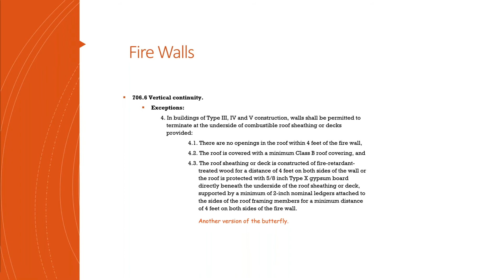The roof is covered with a minimum Class B roof covering, and the roof sheeting or deck is constructed of fire retardant treated wood for a distance of 4 feet on both sides of the wall, or the roof is protected with 5/8 Type X gyp directly beneath the underside of the roof sheeting or deck. And that gyp is supported by minimum 2-inch nominal ledgers attached to the sides of the roof framing members for a minimum distance of 4 feet on both sides of the firewall. It's just another version of the butterfly condition.